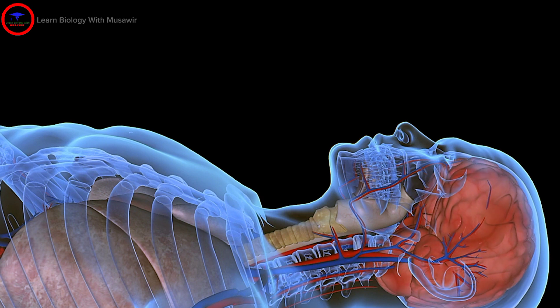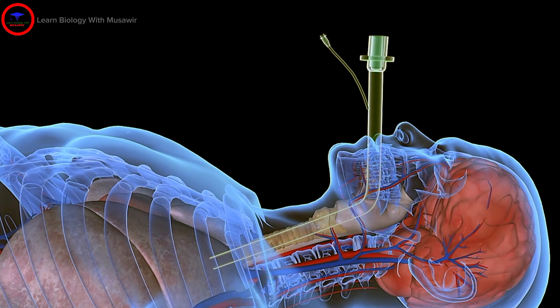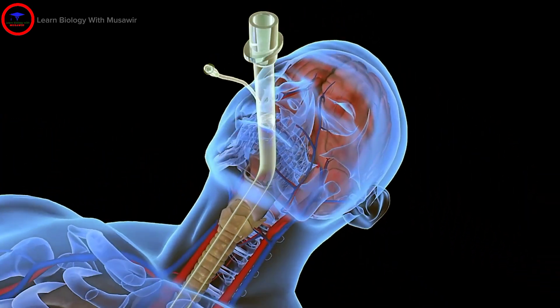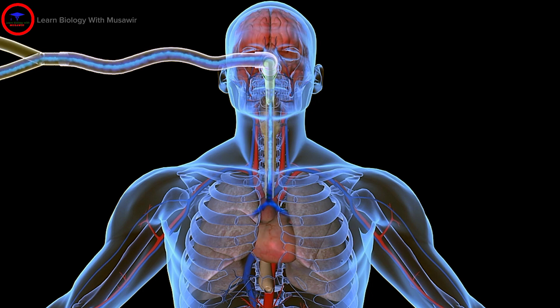Because it uses the patient's own lungs as powerful heat exchangers. First, an endotracheal tube is placed into the airway of the patient. With cardiac rhythm restored or supported mechanically, the liquid ventilation system's delivery tube is connected and the system is activated. The system's computer then begins delivering carefully controlled cycles of ice-cold liquid and oxygen in and out of the patient's lungs.